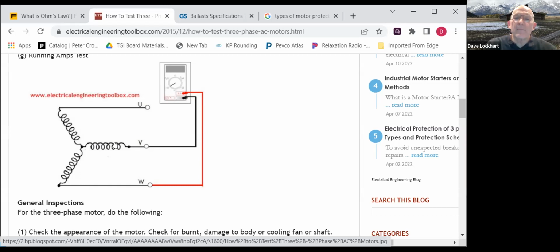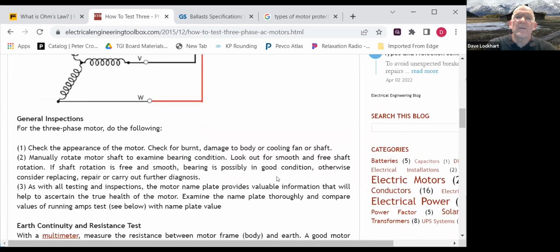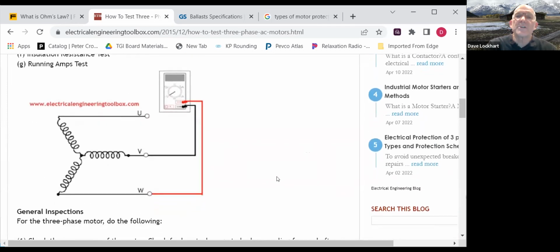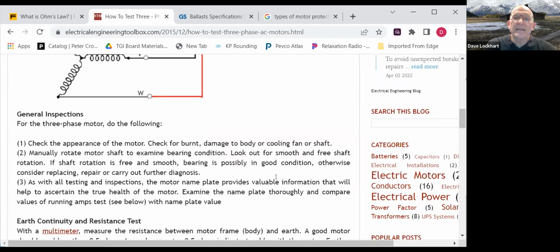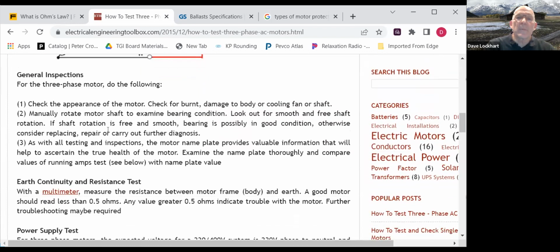To check the windings on a motor, you can take your volt ohm meter and check your ohms across the coils. Make sure you don't have any openings. You can check across the ground. This website I found, Electrical Engineering Toolbox, walks you through how to check a motor. First check the appearance, check for burnt damage to the body, cooling fan or shaft. We often know that lubrication is one of the high failure points for motors. So look at the lubrication and the bearings, manually rotate the shaft, and make sure the bearings are working okay.